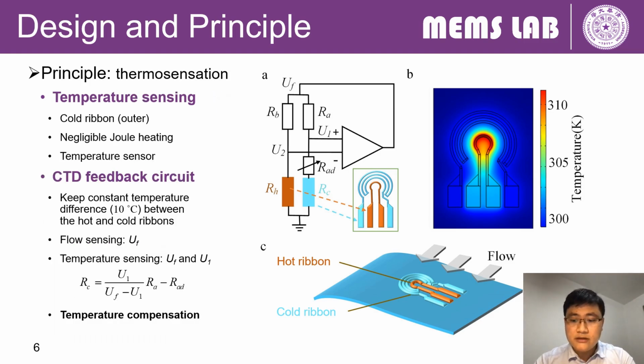The outer ribbon has negligible Joule heating due to its large resistance and thus is called the cold ribbon. It serves as an ambient temperature sensor while working. A constant temperature difference conditioning circuit, which is a so-called CTD circuit, is used to regulate the two ribbons. It maintains temperature compensation for flow sensing.